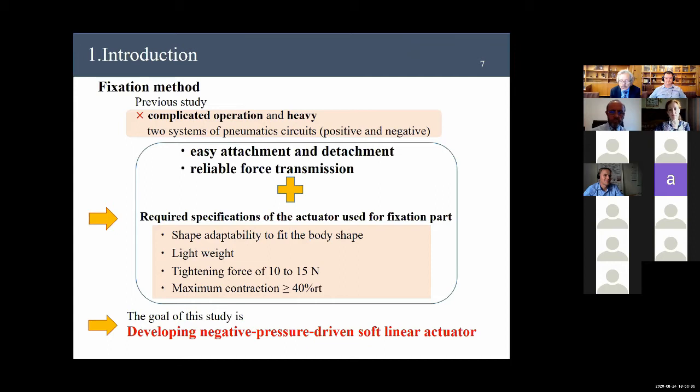Required specification of the actuator is shape adaptability to fit the body shape, light weight, tightening force of 10 to 15 newton, and maximum contraction over 40%. It is determined by preliminary experiments. In the experiment, we determined enough power to fit was around 10 newton, and we subjectively measured the upper limit range of the tightening force that does not feel uncomfortable. The target contraction rate was set to satisfy that parts such as hand and feet pass through the fixed part. In particular, in case of the fixation of the curve, the highest contraction rate is required, and its value is 40%.